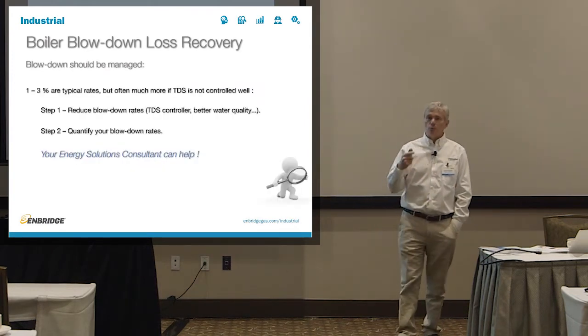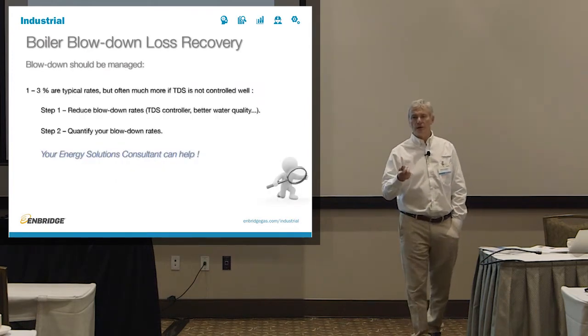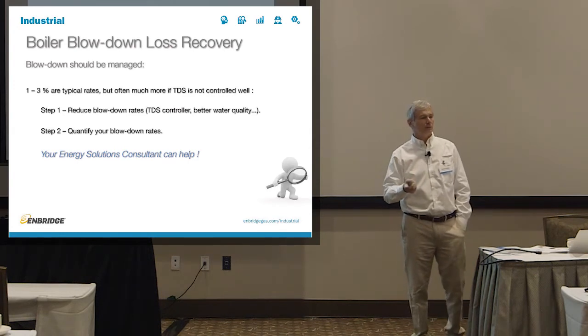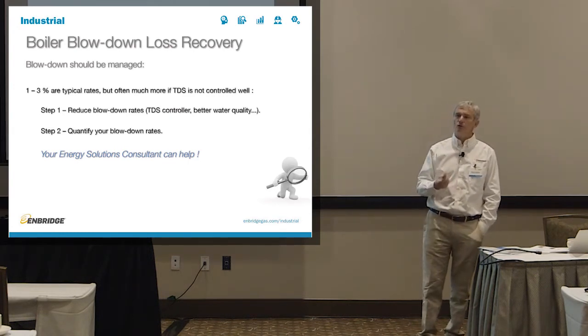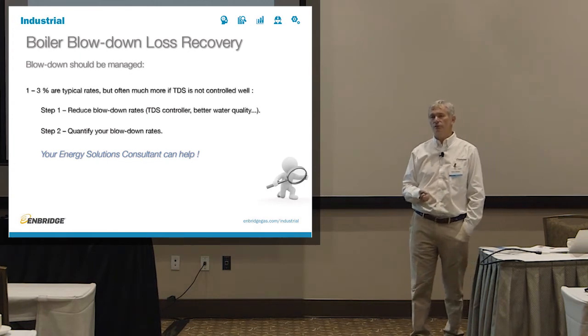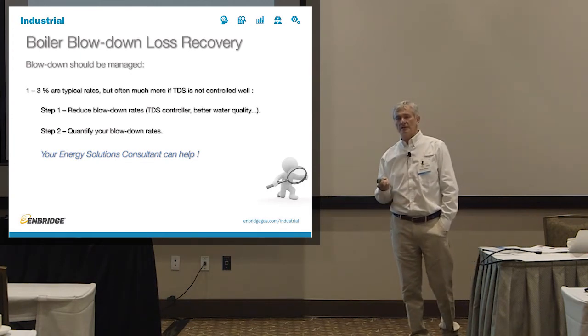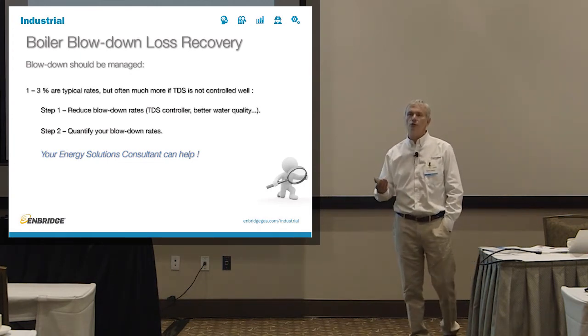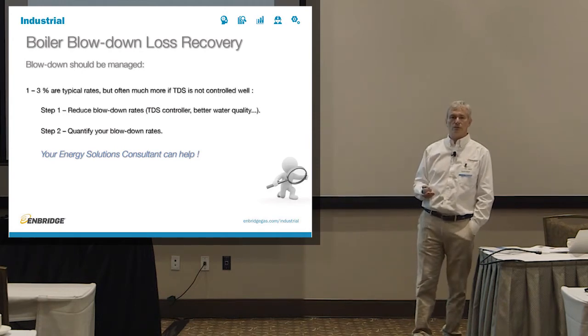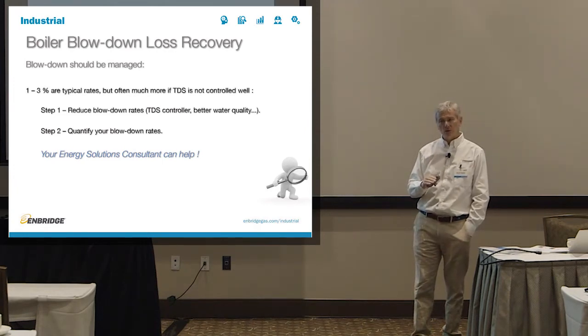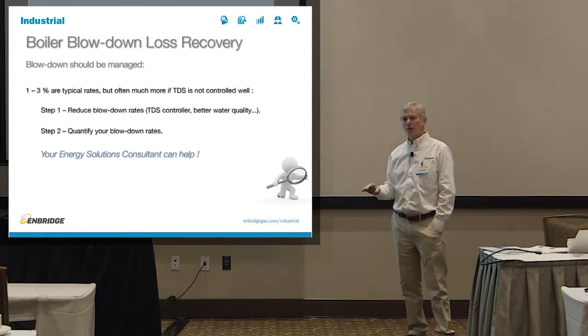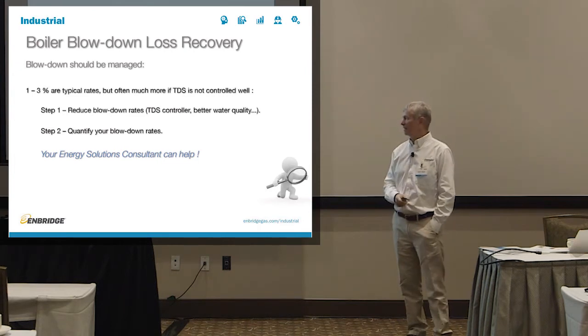So step one, if you find that you have very high blowdown rates, 10, 15%, don't recover the heat off it. Reduce it first. It's nice to recover the heat, but if you don't need to waste it, don't waste it in the first place. Operate your boiler at blowdown levels that are reasonable, then quantify those blowdown rates and then recover the heat. And we can help you out with that.